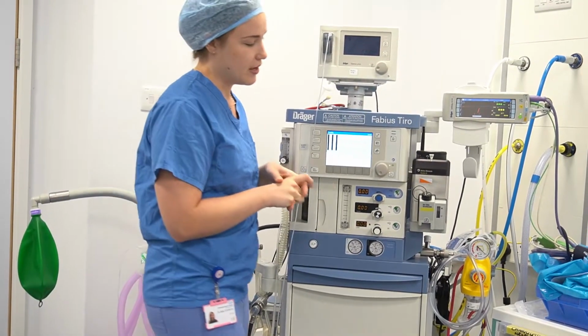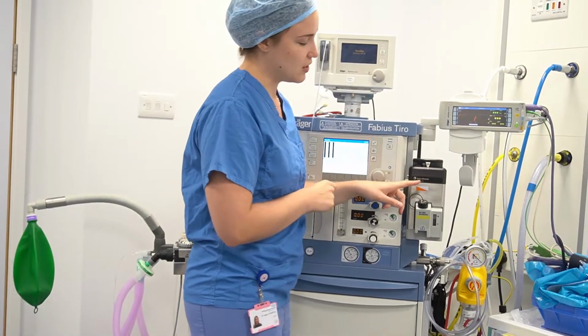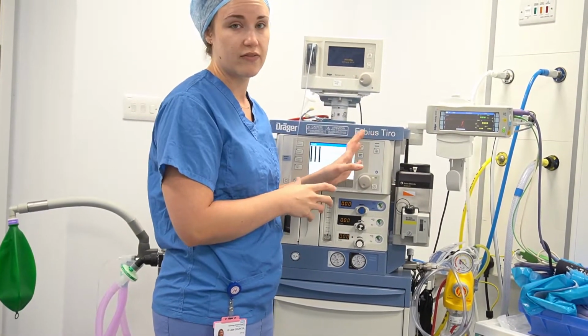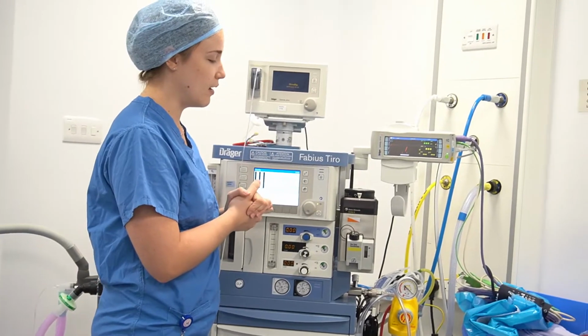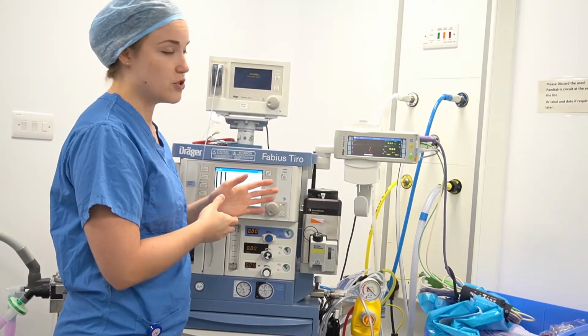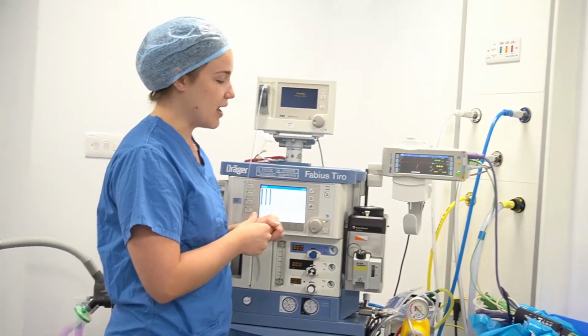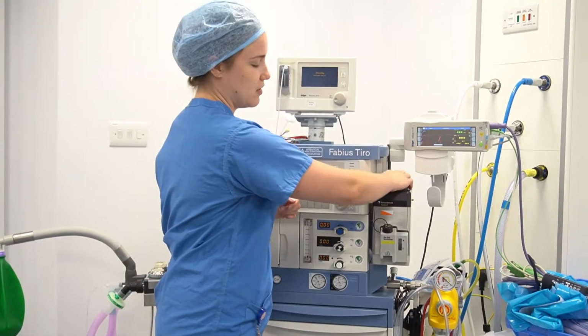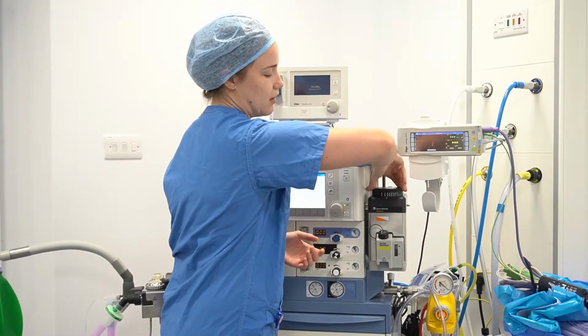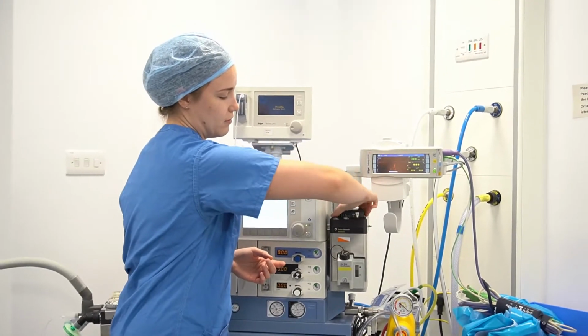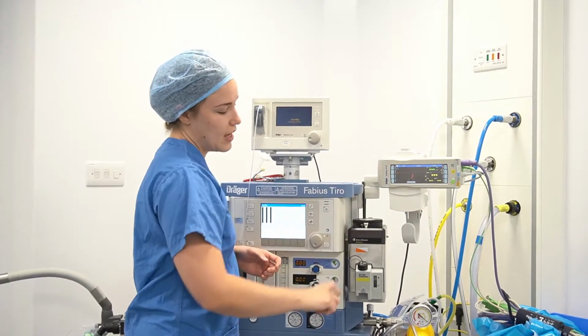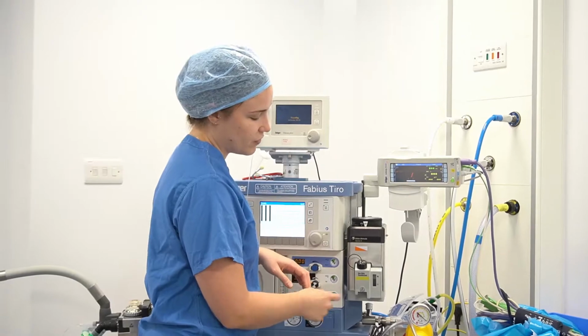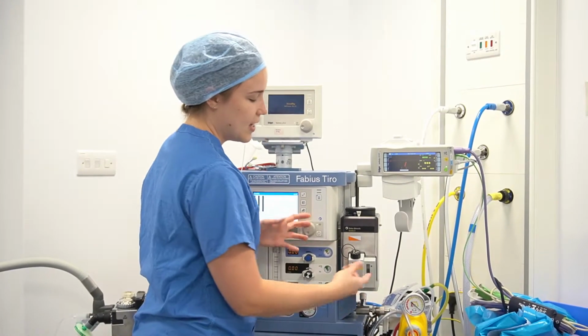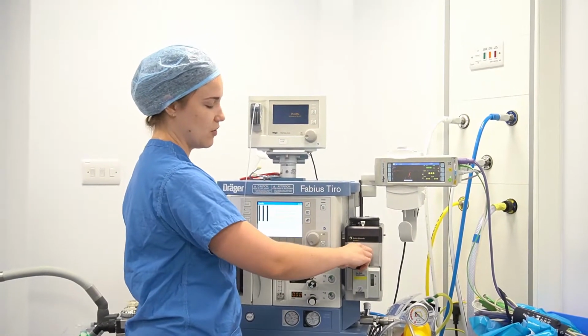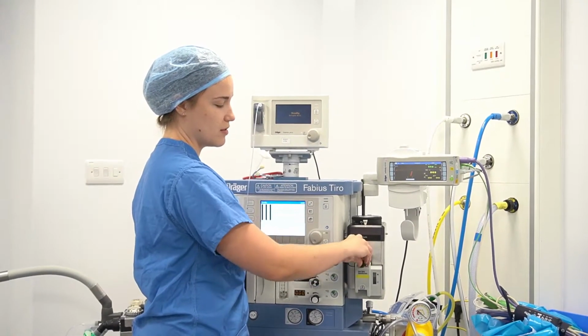And then on this side of the machine, you can see over here that these machines only have a setting for one vaporizer, mostly being sevoflurane, and it's a Tec 5 vaporizer. So you can just check that the dial moves all the way open and locks when it's closed. You can check that it's full by reading the level over here, and if it does need to be replaced, you can just open this and fill it from the bottle.